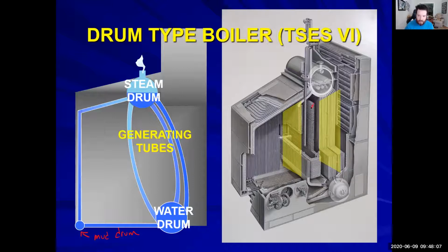All right. What I'm highlighting here in red is not part of the generating tubes. They're on the outside of what I just colored in red, on both sides. You can see there's kind of a wall of it, and then there's a bigger mass on this side. All right. And what I just colored in red is our superheater. So if you look, there's almost 2 tubes there, where this has probably close to 16 or something like that. Those two tubes, their job is to protect the superheater in there.